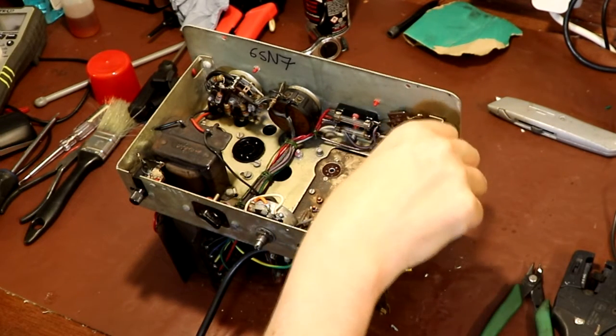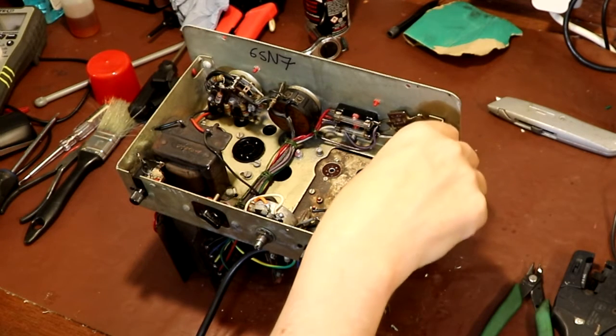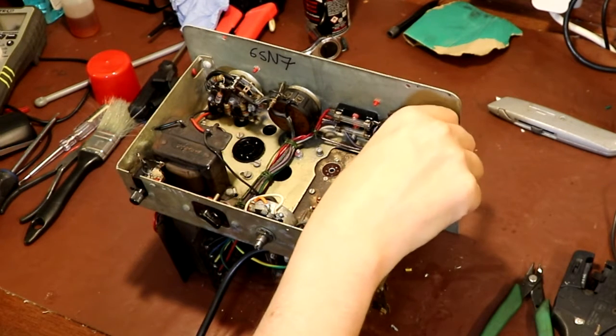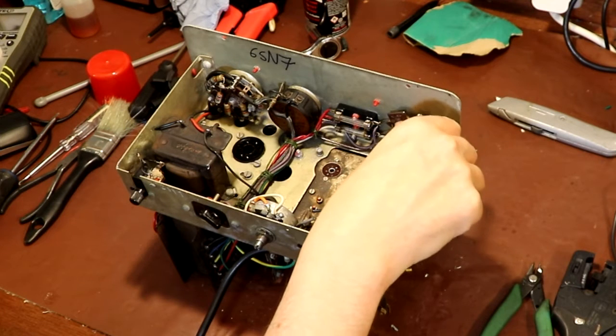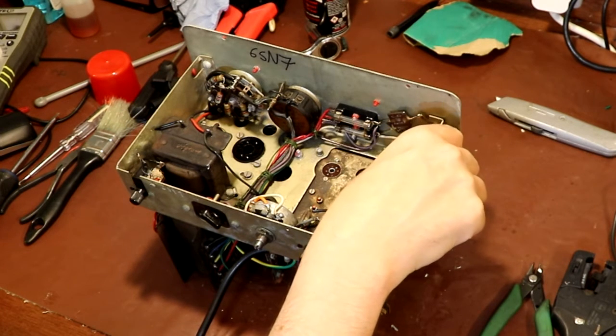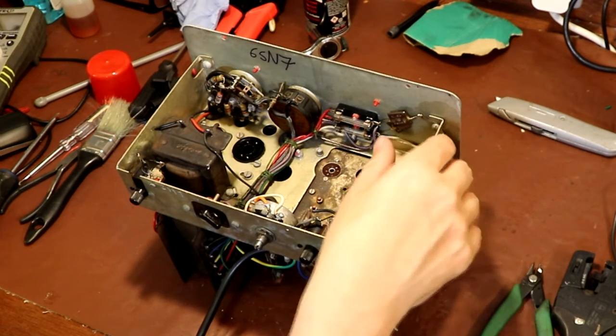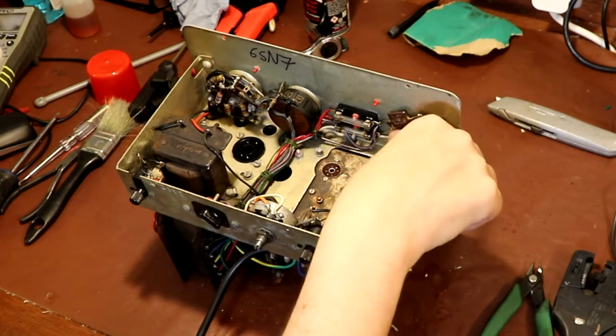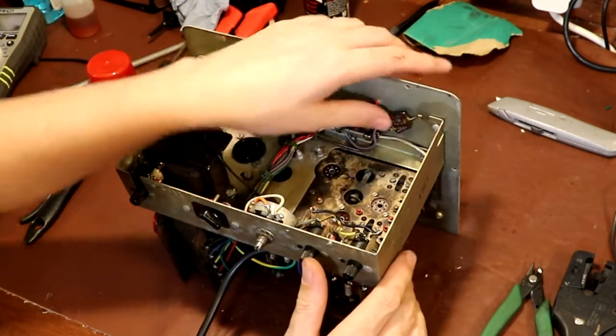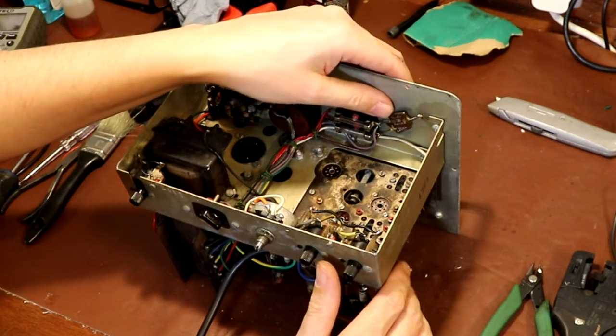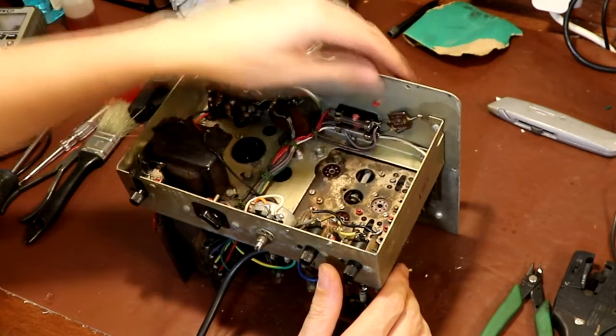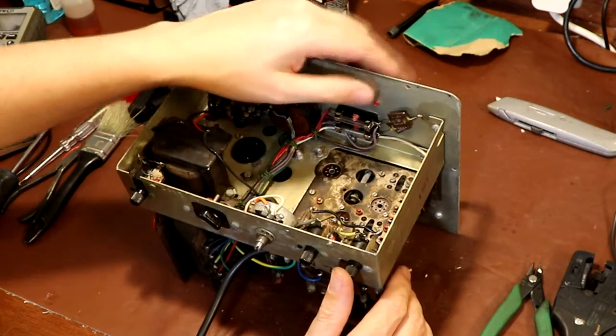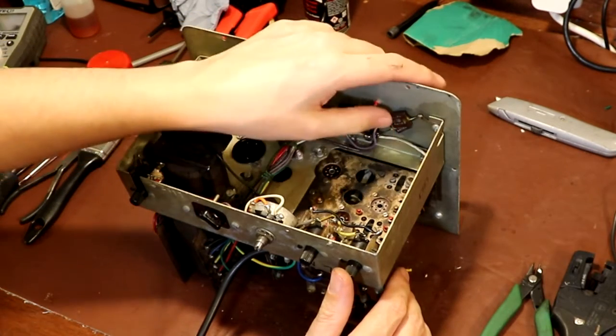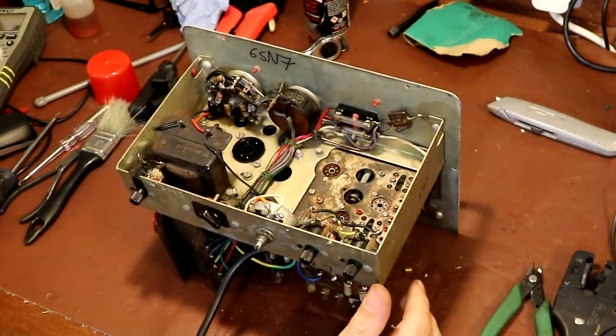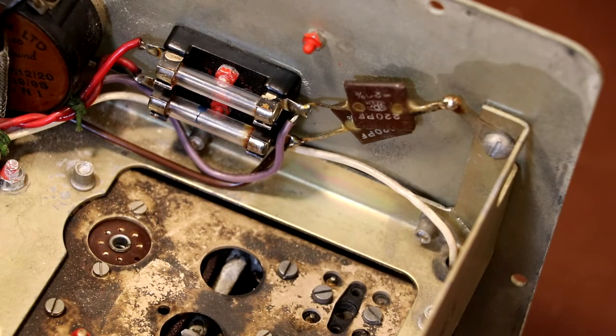And then we've got these two capacitors here, which are EMI capacitors. I think I might have mentioned earlier, the function of these is just to stop RF radiation leaking out of the mains flex and causing problems. But one thing you can almost guarantee is that these tend to explode even on modern equipment and go short circuit, and we certainly don't want these horrible waxy things to go short circuit and maybe start a fire or something.